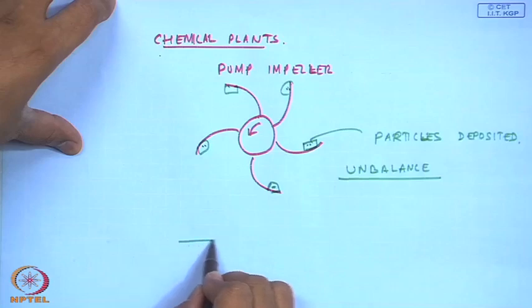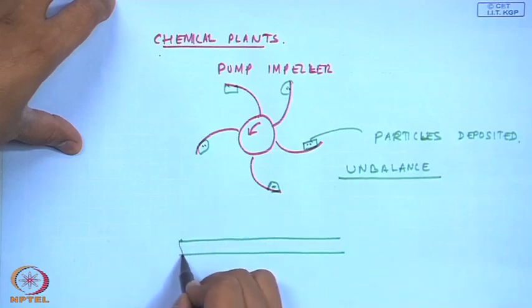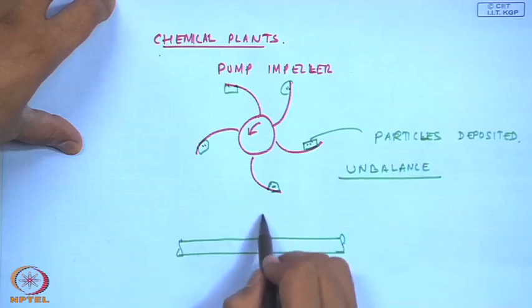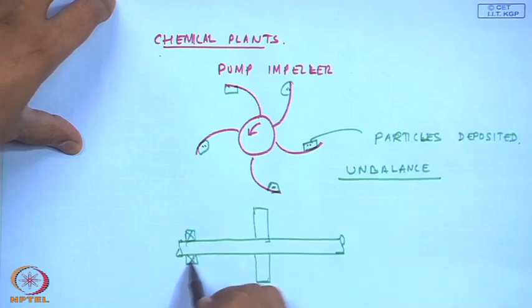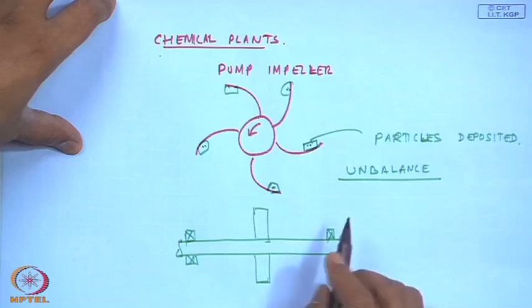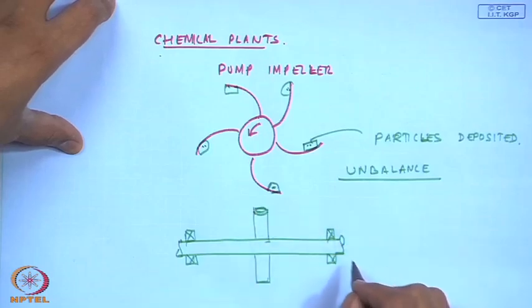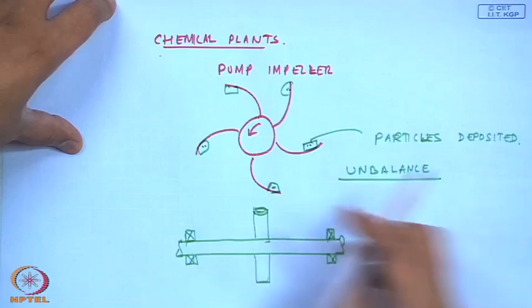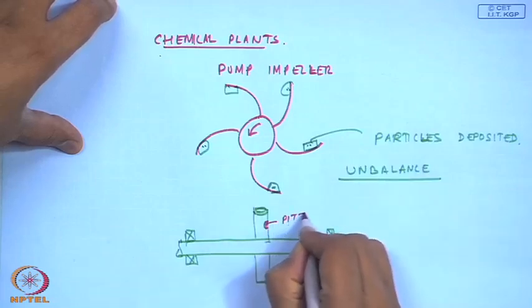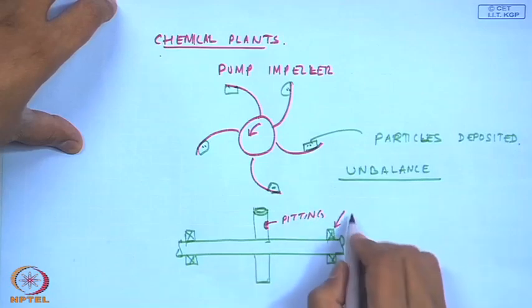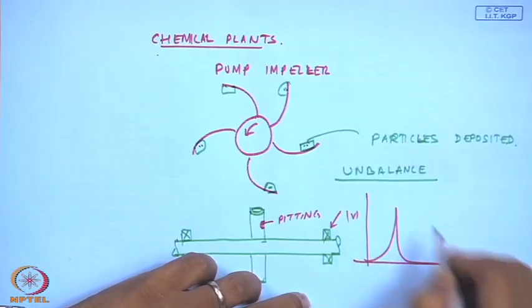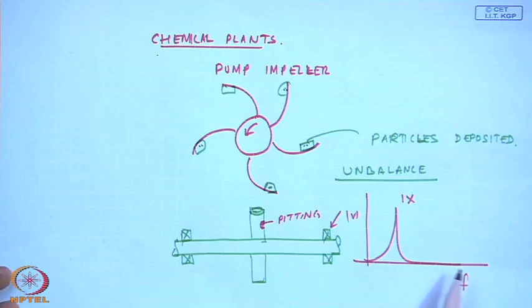So, if I have a shaft, either there can be unbalance or there can be pitting. So, all these will give rise to again the same problem which you see in the frequency of the vibration signal, a strong 1x component.